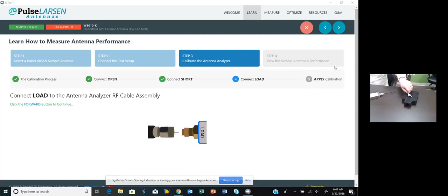The 3 ports are open, short, and load. Generally open, short, load is the order in which people do it, and it's the order we recommend based on convention. Here's short. And here's load. The calibration process takes a little bit of time, but any RF engineer will tell you it's critical to making sure your measurements are accurate. Now I'll hit next. If you've made a mistake along the way, you can go backwards to correct it. You can hit the red X button to restart your calibration at any time. I'm going to hit the green check mark to say that I've calibrated it correctly.